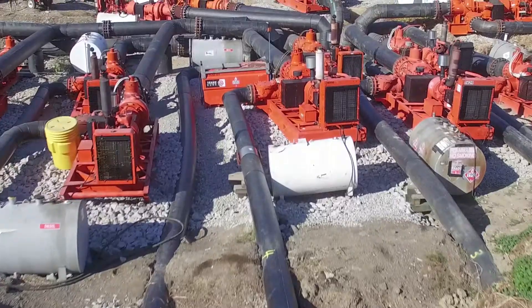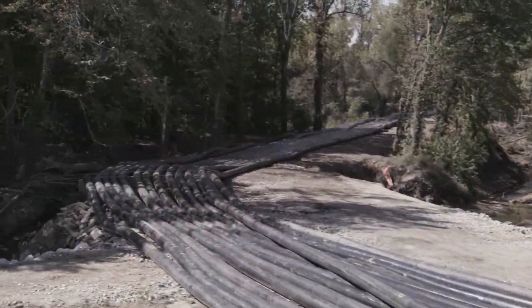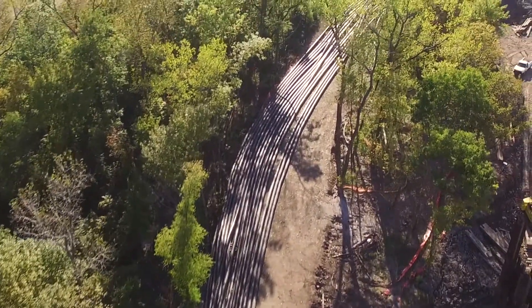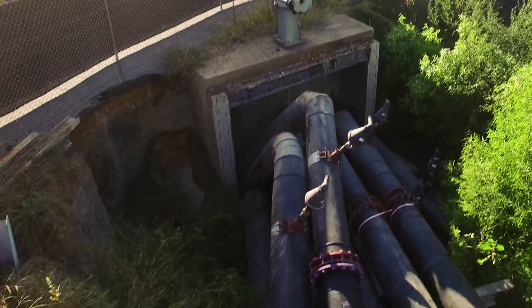With Xylem's unique knowledge of this area and the sewer system, we knew there was an access point where the pumps are located. We were able to take that access point, set up our pumps there, route the pipe across the access road that we installed, and discharge into one of their gate structures about 2,200 feet away from the suction point.